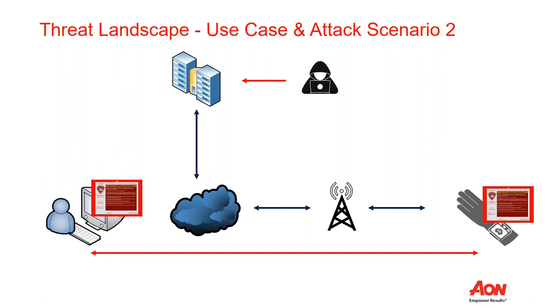There was a good real-world example of this demonstrated in 2018 by a couple of security researchers who took a look at a pacemaker system and the network infrastructure that supported it. They discovered vulnerabilities in the software delivery network used to deliver updates to the pacemaker programmer devices, which health professionals use to configure pacemakers and tune parameters for each specific patient. By compromising the delivery system, they showed they could deliver a malicious software update to the pacemaker programmer.